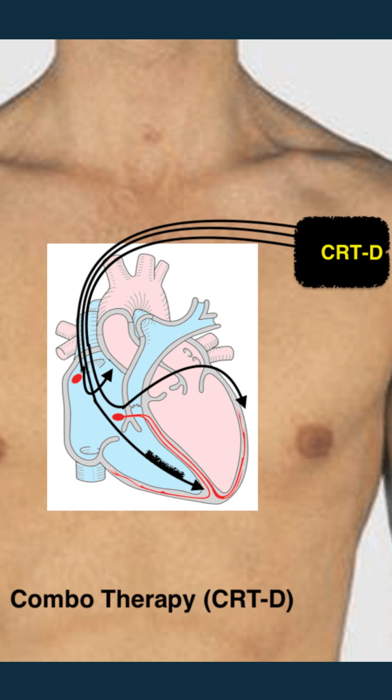This is a CRTD, called a cardiac resynchronization therapy defibrillator of the heart, and it is implanted under the skin below the collarbones. The usual time of implantation is 2 to 3 hours depending on the expertise and the patient. There are 3 ports which will be connected with 3 leads implanted in the right upper, right lower, and left side of the heart.